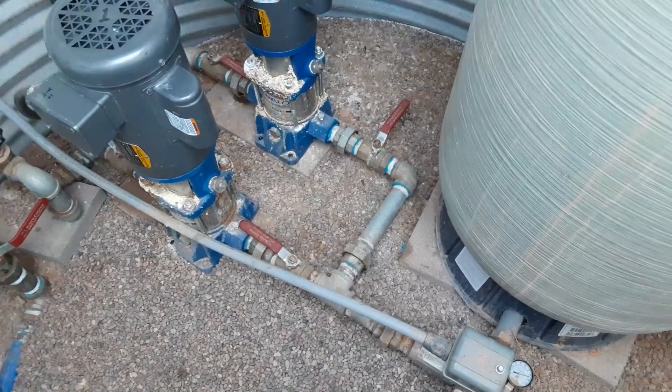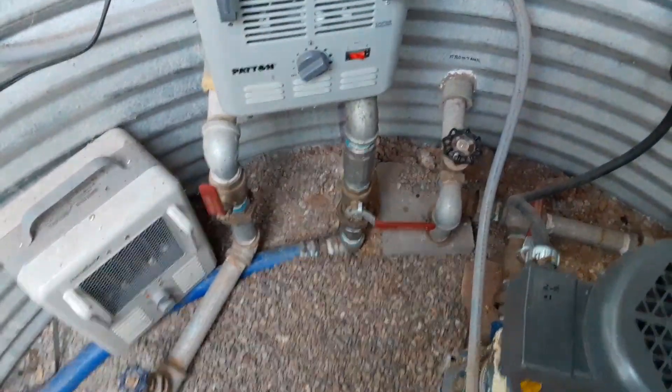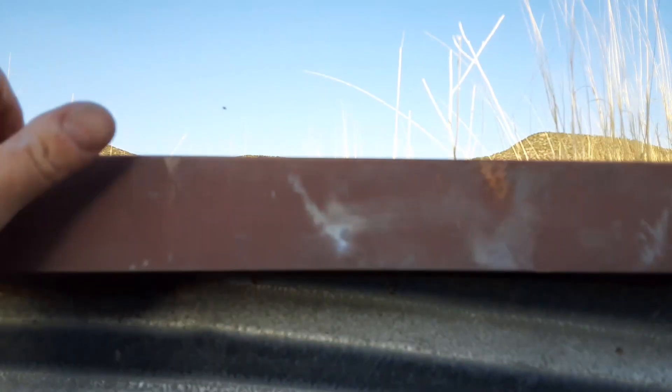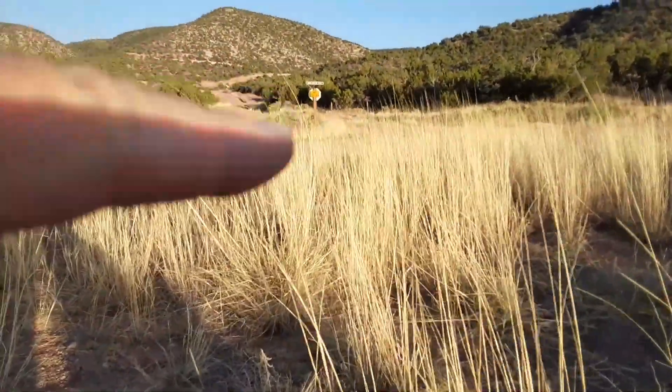What I'm going to do next is continue testing outward from here to see if there's any kind of real leak. The next step is to open up the water from this system and let it go out towards the two mains and their shutoffs — I've already retightened them to make sure there's hopefully no possible leak. I'll open this up, let the water go out to the street to those two mains, let it sit overnight — maybe a full 24 hours — after I turn the power on here for a little while and re-pressurize everything, then take a reading. That'll tell me if there's any kind of leak between the pump system in here and the mains out in the street.